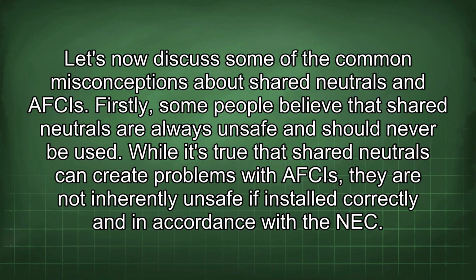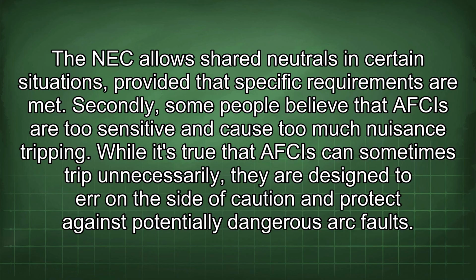Firstly, some people believe that shared neutrals are always unsafe and should never be used. While it's true that shared neutrals can create problems with AFCIs, they are not inherently unsafe if installed correctly and in accordance with the NEC. The NEC allows shared neutrals in certain situations provided that specific requirements are met.